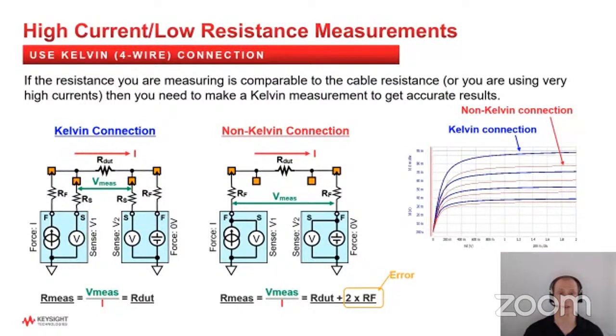And you can actually see on that ID-VD family of curves, there's obviously a very distinct difference between a measurement made with a Kelvin connection, which is giving the correct data, and the non-Kelvin connection in red, which is showing an erroneous measurement. And it's an error because it's measuring the resistive drop in the cables. So again, it's important for these situations to understand when you should and should not use a Kelvin measurement.